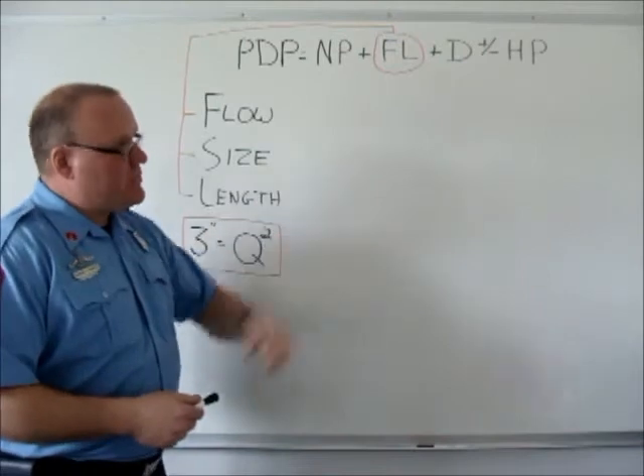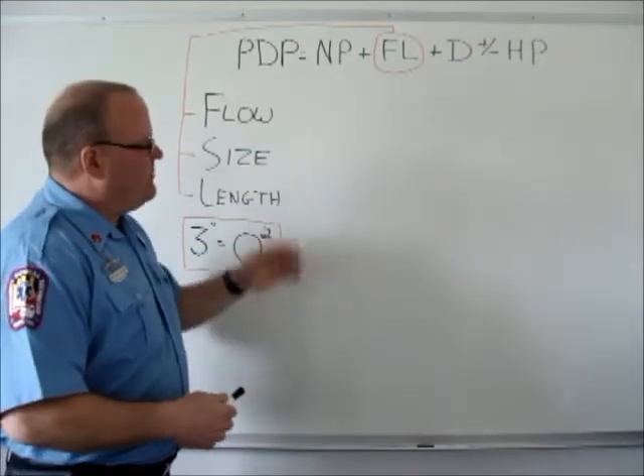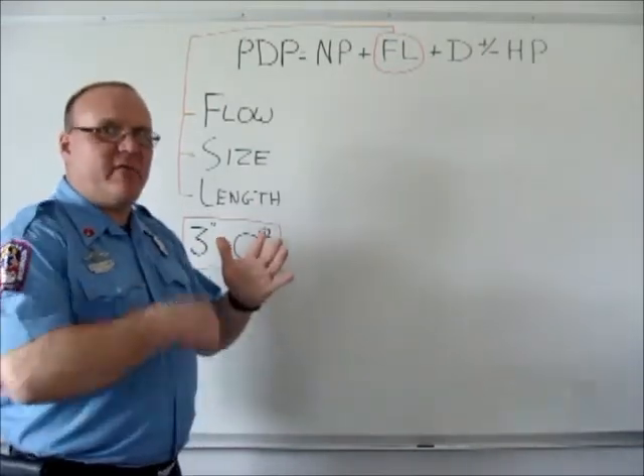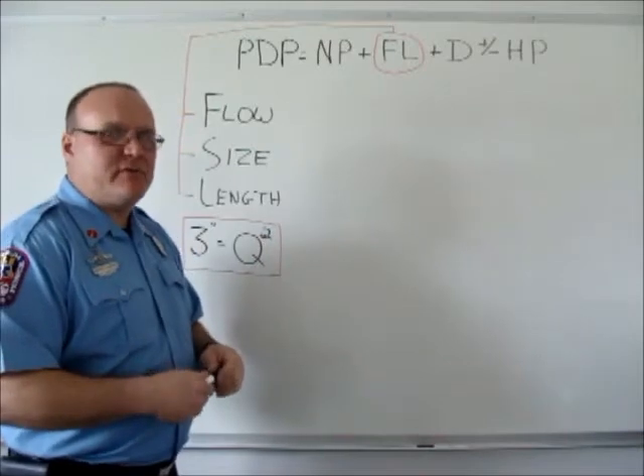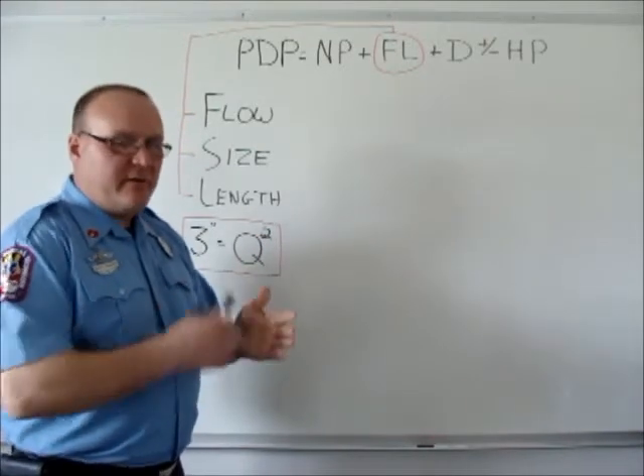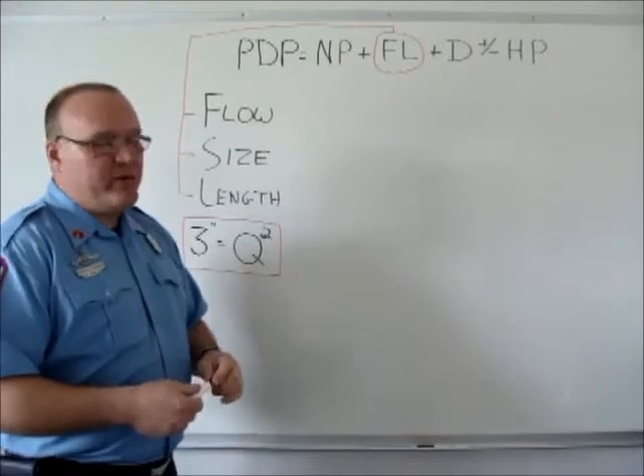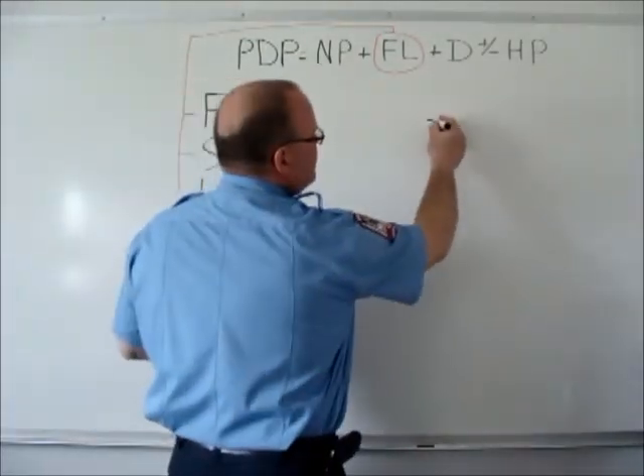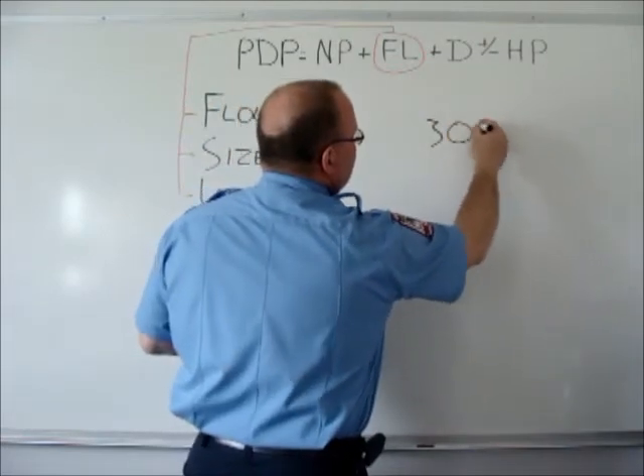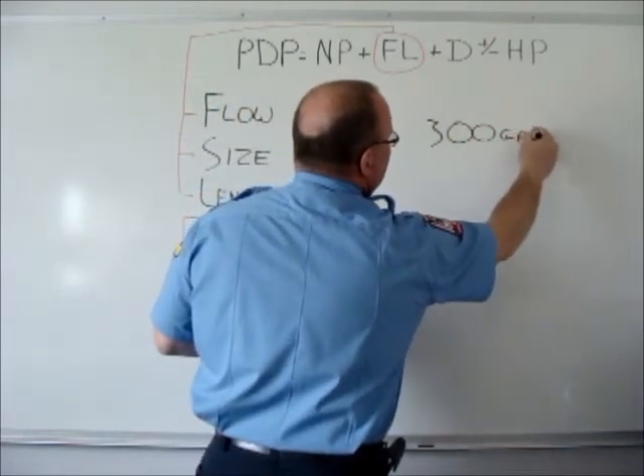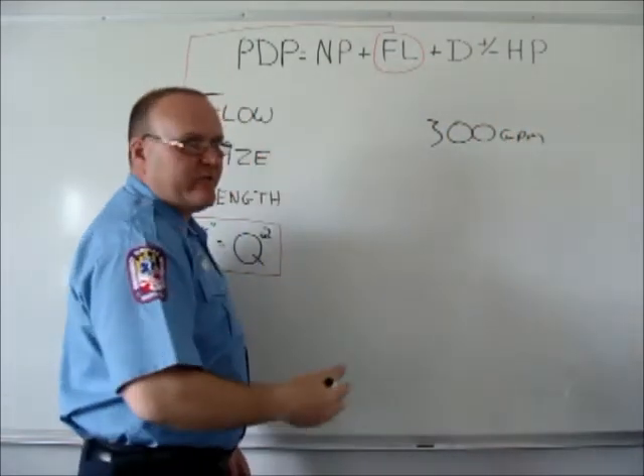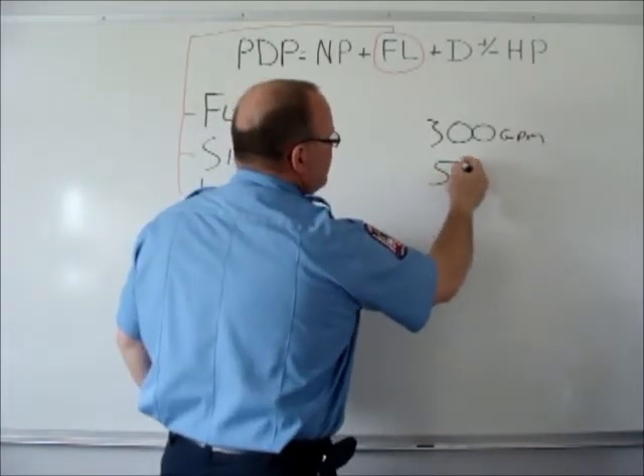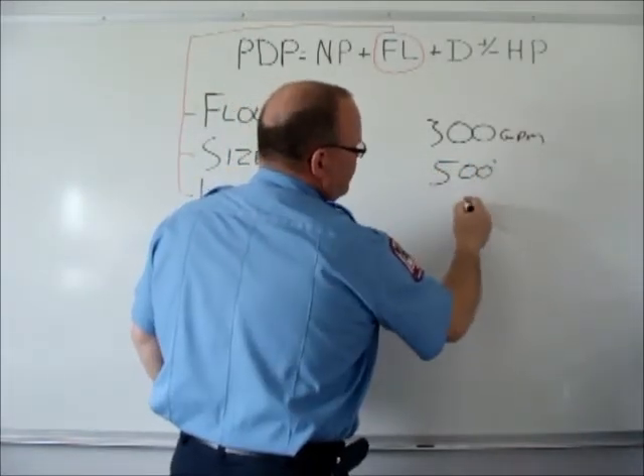We'll do a couple of examples here for three inch hose and then we'll show you how this translates to a hand method that a driver operator can use at 2 o'clock in the morning on a fire as a memory jogger. So the first example we'll use, we'll say 300 gallons a minute and we'll say that it's 500 feet of three inches.